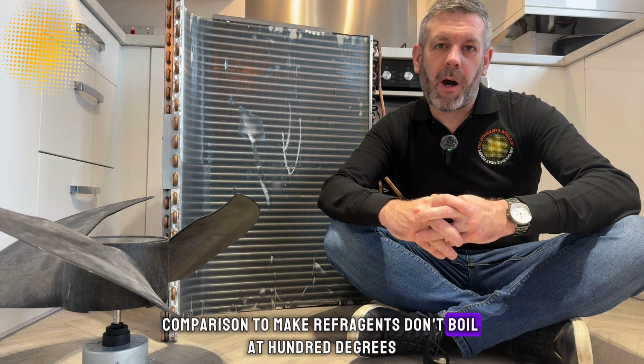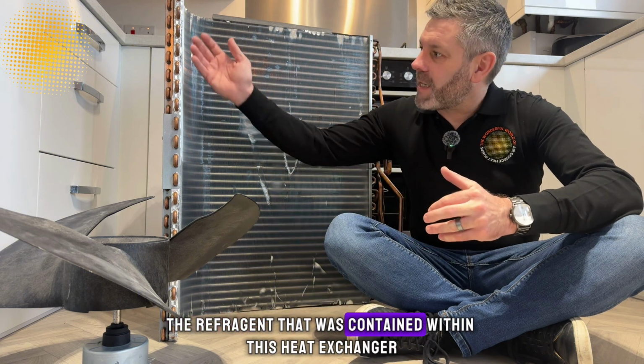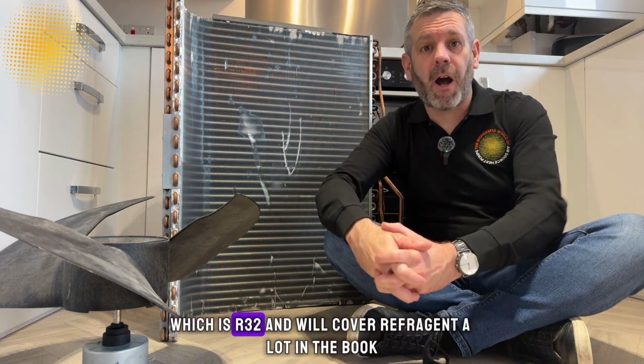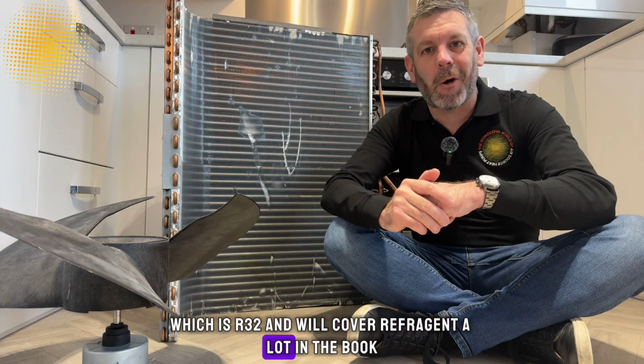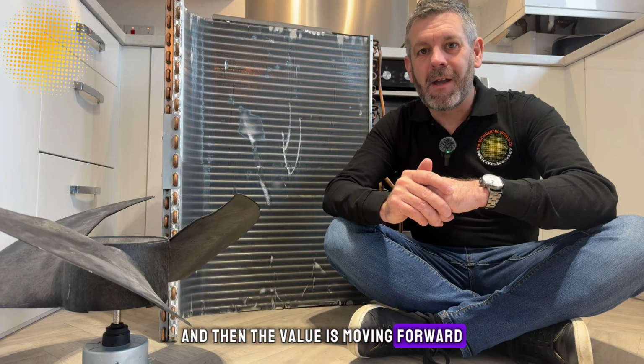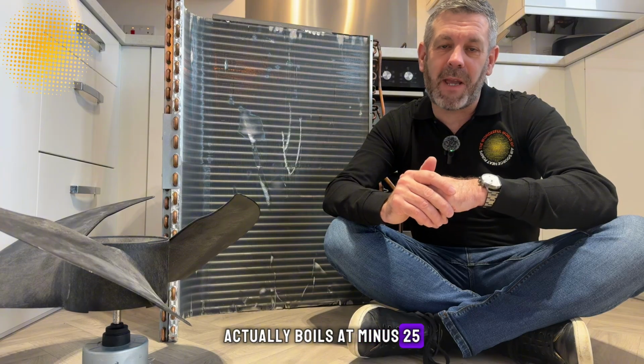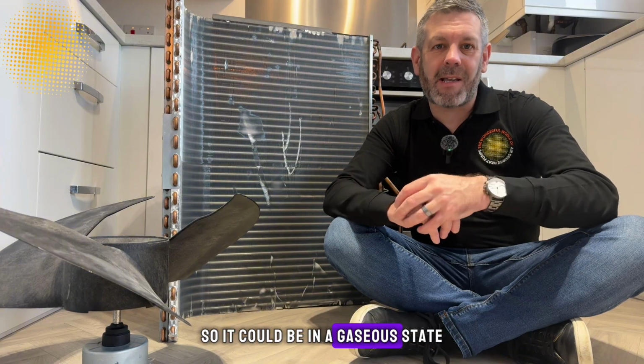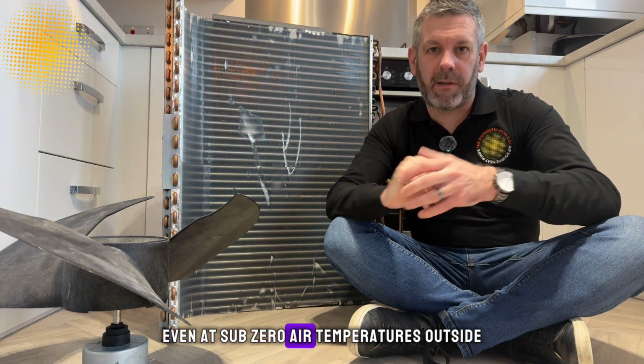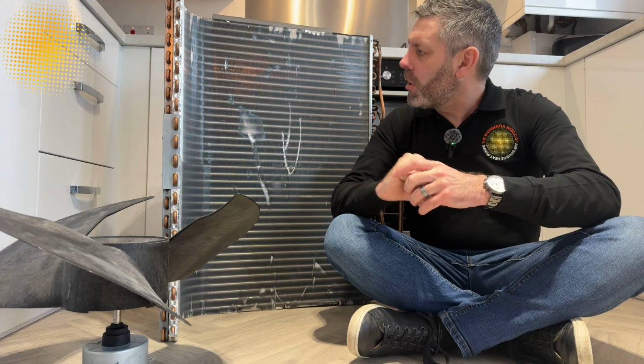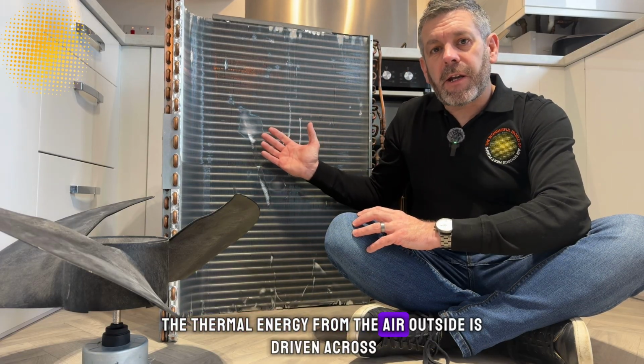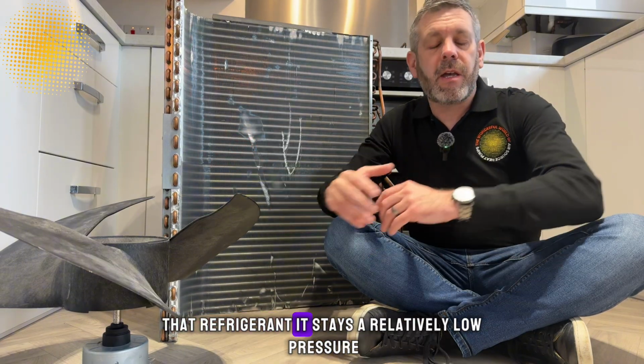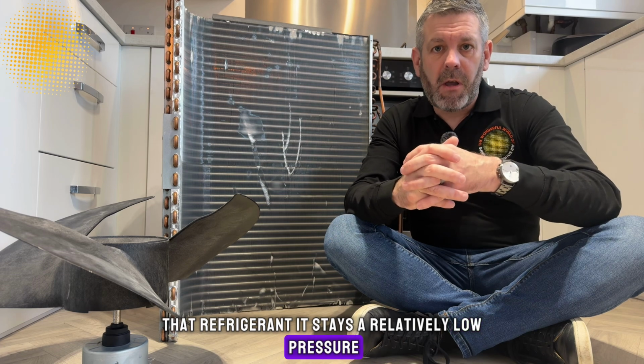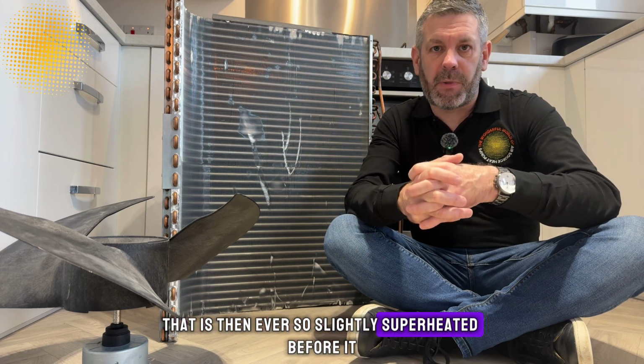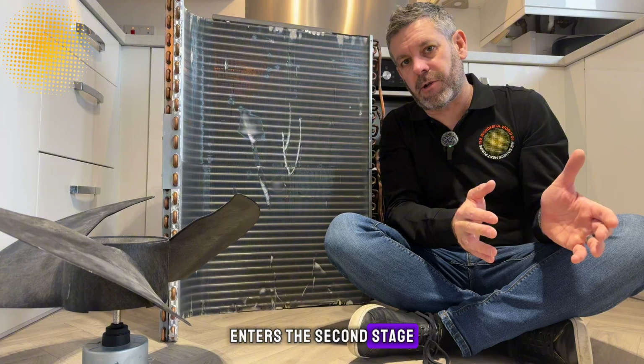Refrigerants don't boil at 100 degrees. The refrigerant contained within this heat exchanger, which is R32, and we'll cover refrigerant a lot in the book and in the videos moving forward, actually boils at minus 25. So it could be in a gaseous state even at sub-zero air temperatures outside. The thermal energy from the air outside is driven across the heat exchanger to boil that refrigerant. It stays at a relatively low pressure, but is then ever so slightly superheated before it enters the second stage.